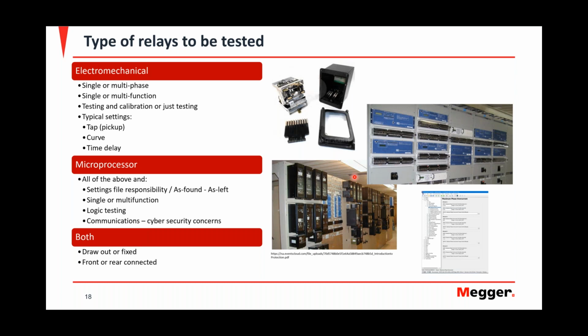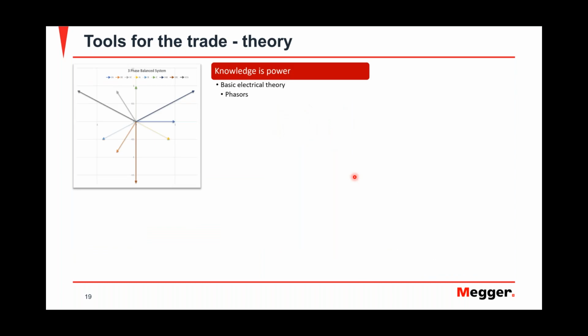Are they connected through the front or rear? And by front, I mean, do you have test switches? Because if you don't have test switches and you have to connect from the back, then you really are going to need a shutdown, because you're going to pull those wires out. You could isolate maybe your currents, but your voltages, you might not be able to do that. So those are things to keep in mind on how the testing goes around.